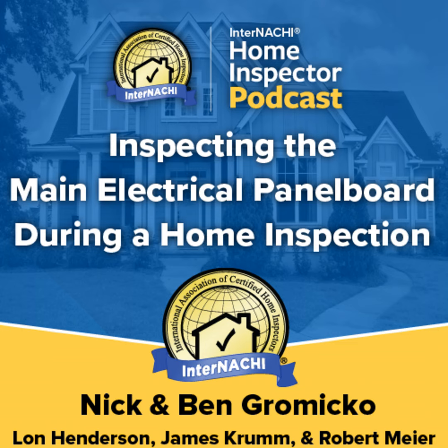Inspectors should always look for a means to secure backfed breakers. A missing retaining device would be a defect. Surge protector. Whole house surge protectors should be installed on new panel boards. A surge protector protects the home circuits in the event of a power surge through the service conductors, such as from a lightning strike. They are frequently seen added to existing panel boards.